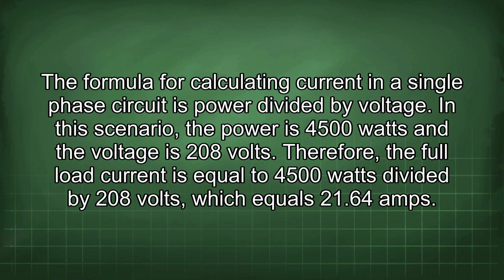The formula for calculating current in a single-phase circuit is power divided by voltage. In this scenario, the power is 4500 watts and the voltage is 208 volts. Therefore, the full load current is equal to 4500 watts divided by 208 volts, which equals 21.64 amps.